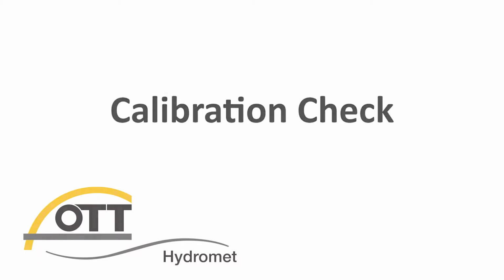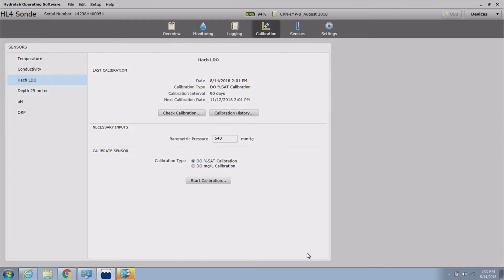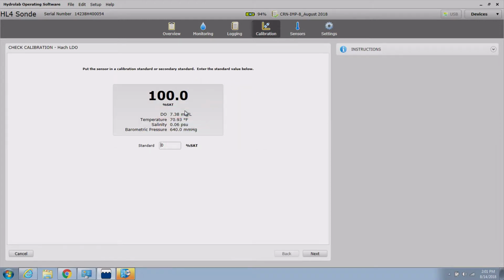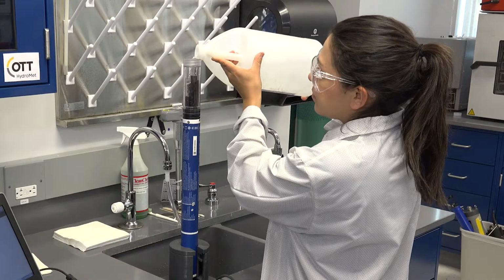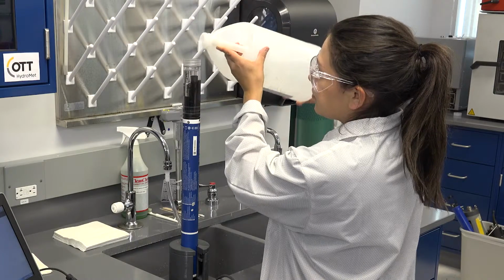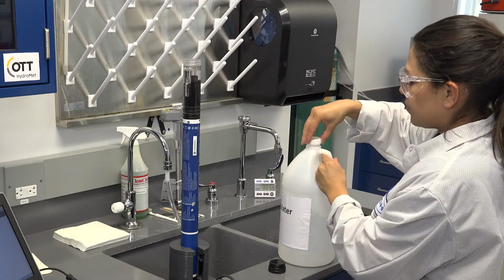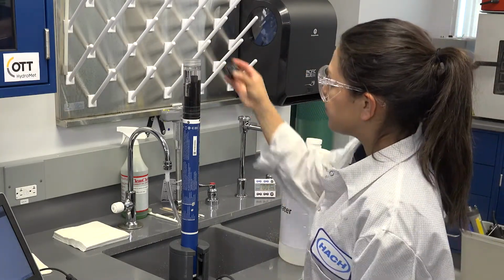Calibration check. After calibration, it is recommended to perform a calibration check to verify that the sensor slope is correct. You can access the calibration check in the Calibration tab of the Hydrolab operating software. Follow the instructions on the right side of the screen. Be sure to follow the same steps of rinsing the sensor in deionized water as well as rinsing with the selected standard for optimal results.